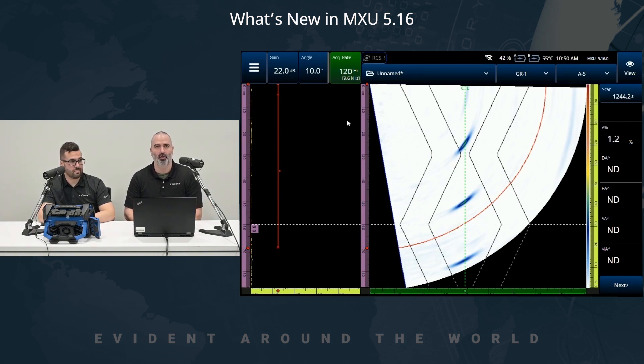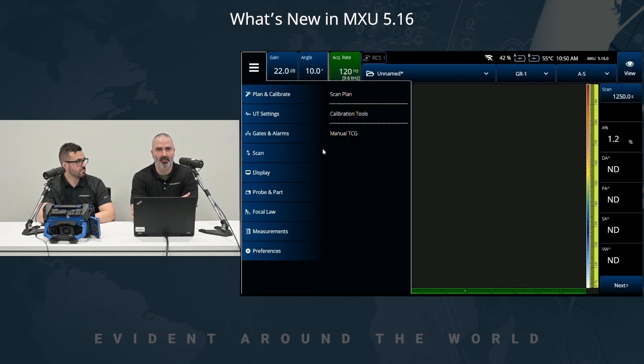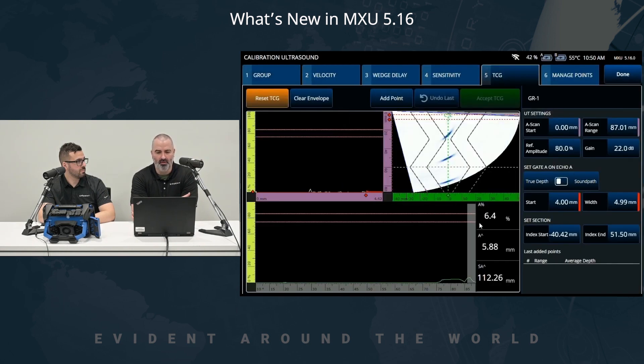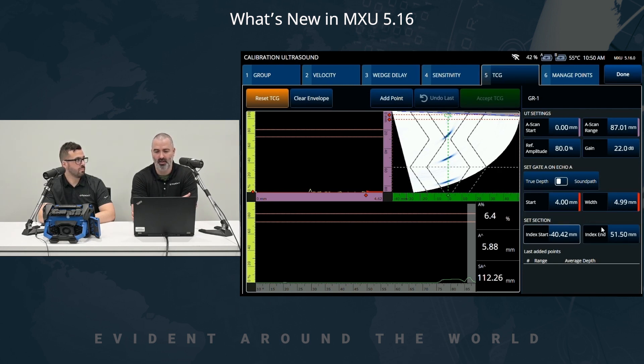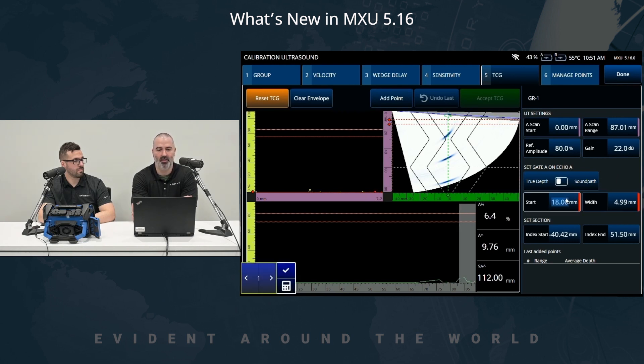To do that, we go into the calibration tool menu and select the TCG calibration tab. We have the same environment as before — the amplitude trace at the bottom, the A-scan, and the S-scan. We now have the ability to select between true depth and sound path gate, and also to move our gate on the depth axis and on the index axis, which are those index limiters I was referring to.